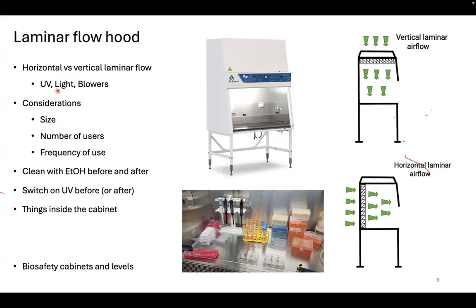And of course, there's going to be UV, which is ultraviolet light. Now, ultraviolet is super dangerous. So you should not be anywhere close to that system where the ultraviolet light is on, nor should your cells be there. But before and after, or before or after, depends. This can be very lab specific, work specific. You have to switch on the UV light for about 30 minutes or so. So in a lot of places, the general practice is once you're done, you UV the cabinet, you close it and you UV the cabinet for some time. So it's ready to use for the next user.